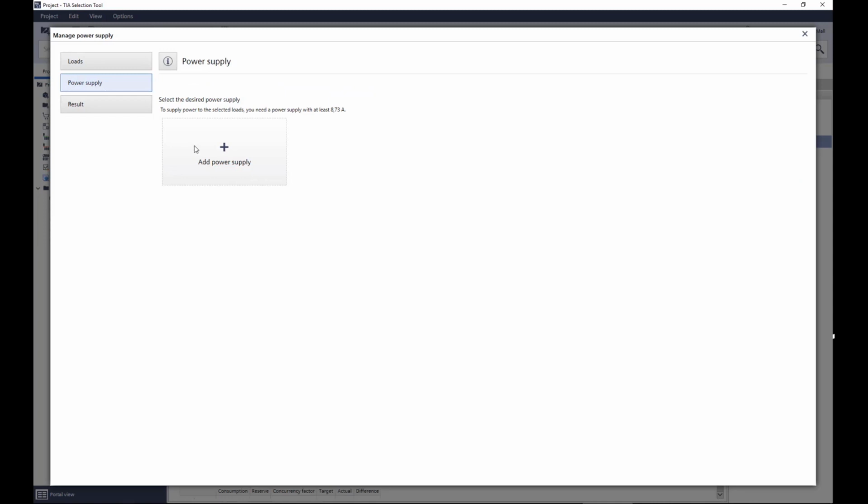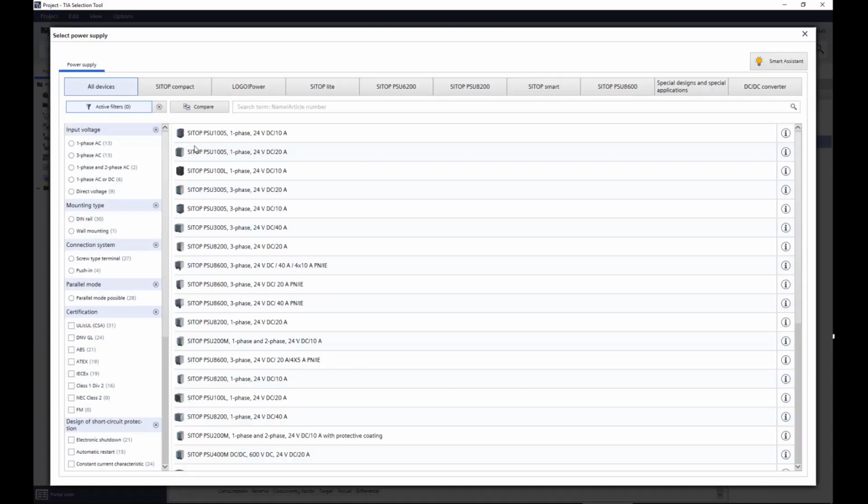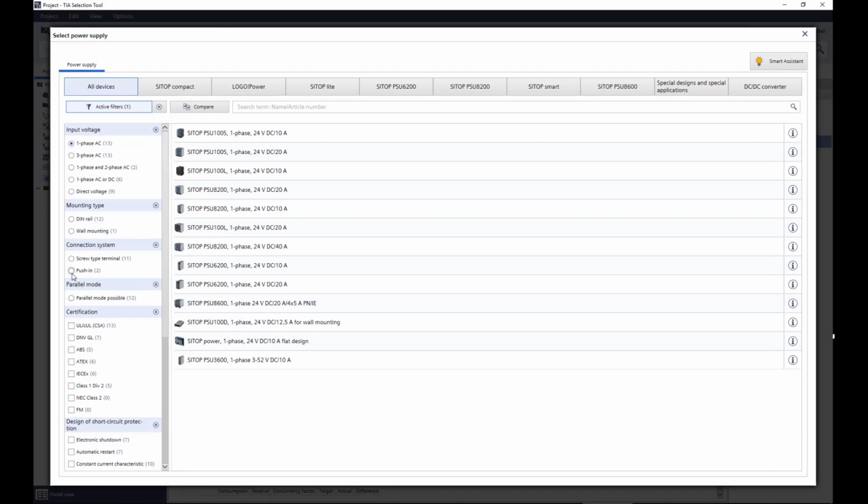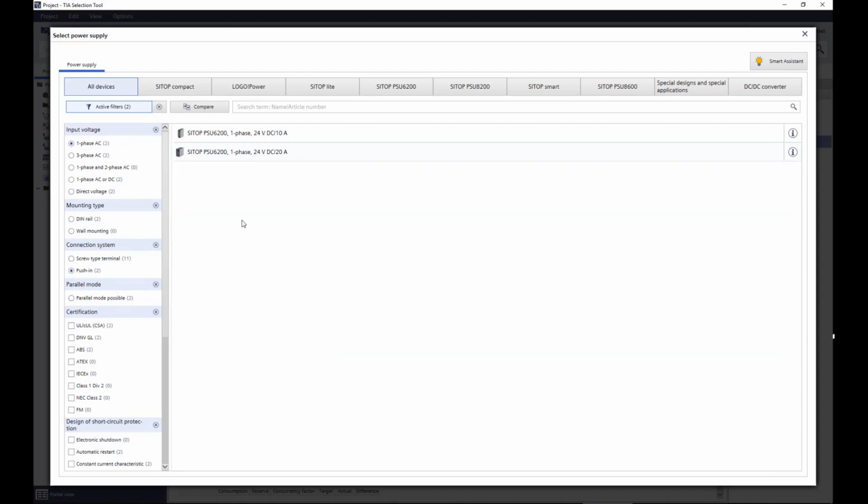All devices with an output current greater than 10 amps are listed in an overview. On the left side, the selection can be reduced and specified using filters. A single-phase power supply with push-in terminals is now selected for this project. The selection of the proposed devices is now significantly reduced and it can be chosen between the 10 amp or 20 amp variant.